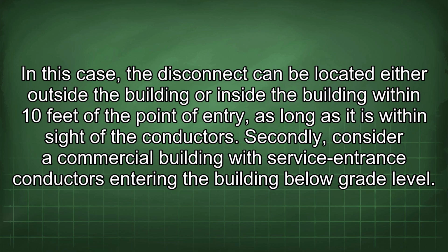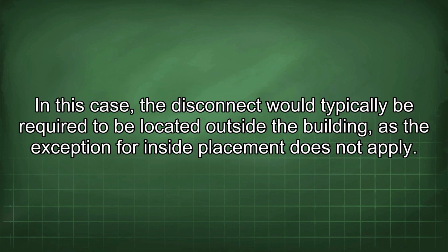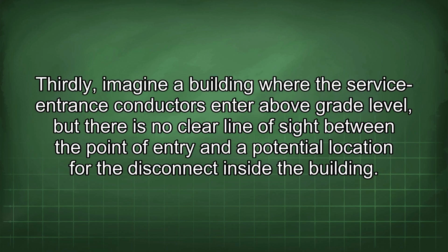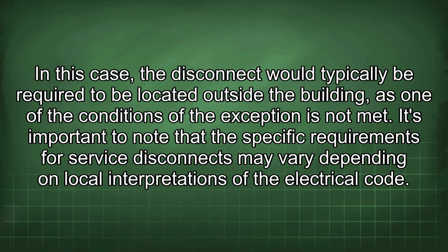Secondly, consider a commercial building with service entrance conductors entering the building below grade level. In this case, the disconnect would typically be required to be located outside the building, as the exception for inside placement does not apply. Thirdly, imagine a building where the service entrance conductors enter above grade level, but there is no clear line of sight between the point of entry and a potential location for the disconnect inside the building. In this case, the disconnect would typically be required to be located outside the building, as one of the conditions of the exception is not met.